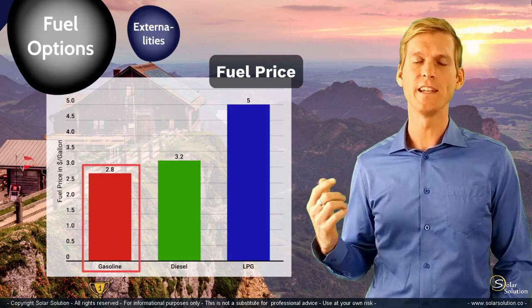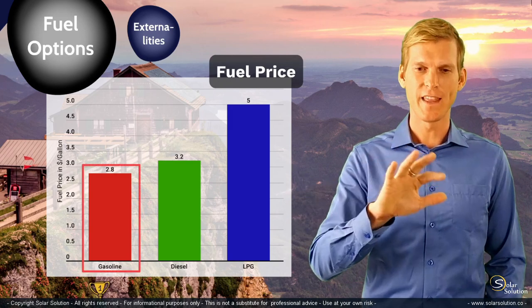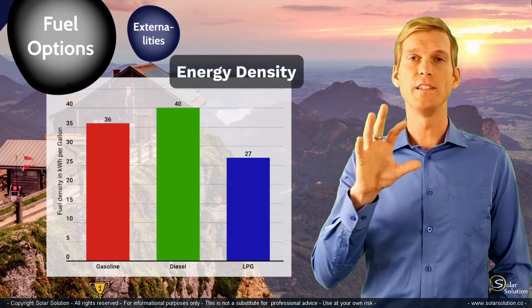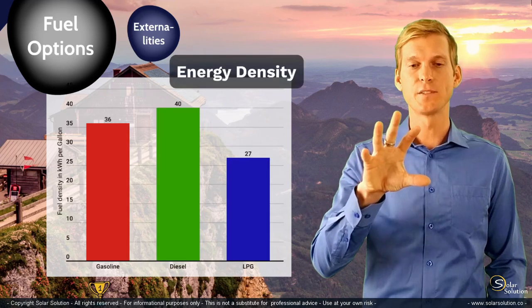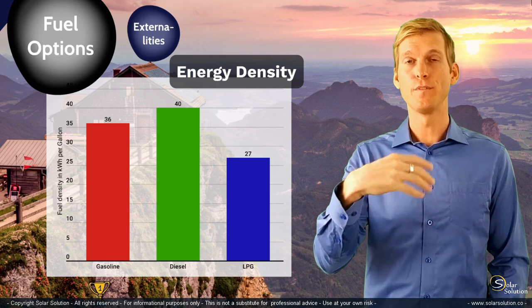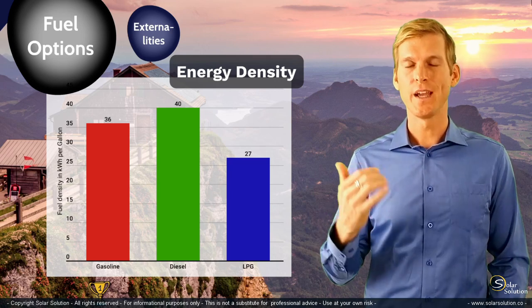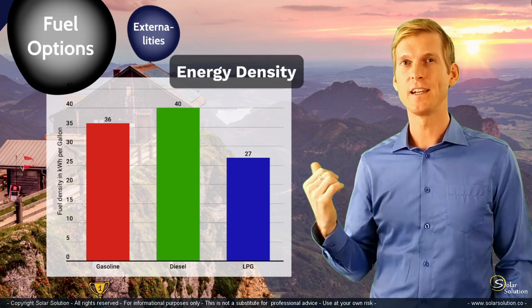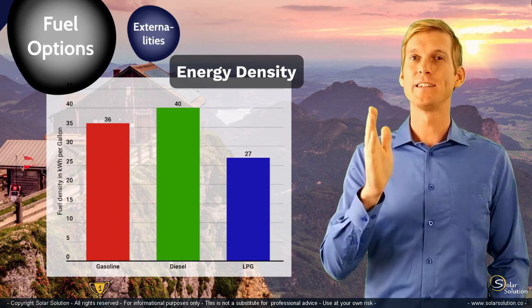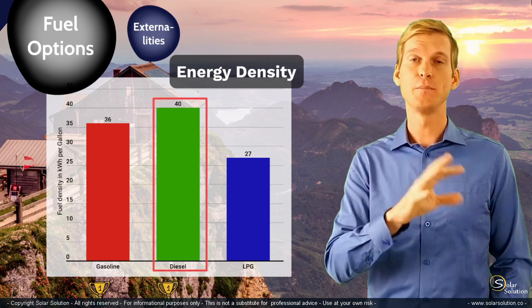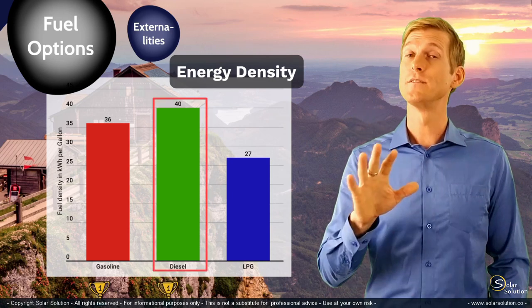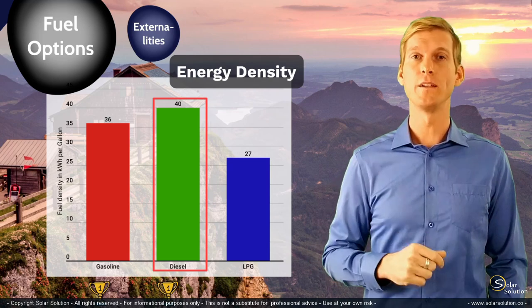But if you look at the energy density, the situation shifts a little bit. In this graph the energy density is expressed as the amount of kilowatt hours per volume per gallon of fuel. And you can see here clearly — maybe not surprisingly — that diesel has the highest energy density per gallon. So by means of energy density, diesel is the clear winner.